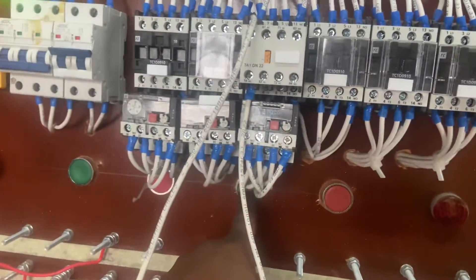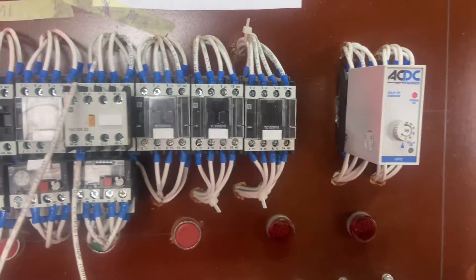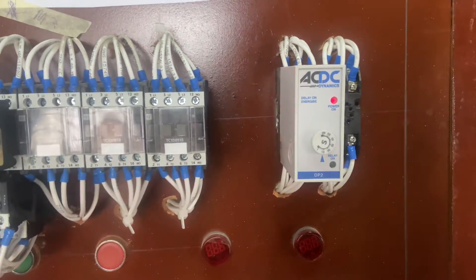Let's start Motor 1 and then wait 10 seconds for Motor 2, because if Motor 2 goes on before the 10 seconds, you have failed. Waiting for the delay-on timer — there we go.